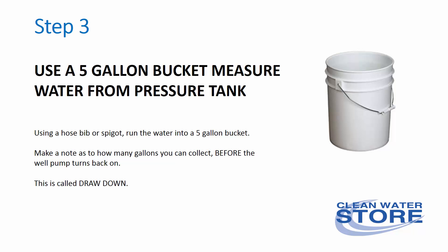Using a five gallon bucket or other container, measure the water from the pressure tank. Run the water from the pressure tank out of a hose bib until you hear your well pump click and turn back on again. You're measuring how many gallons come out of your pressure tank until the well pump turns on — this is called drawdown. Usually it'll be somewhere between five and 20 gallons, depending on the size of your pressure tank.